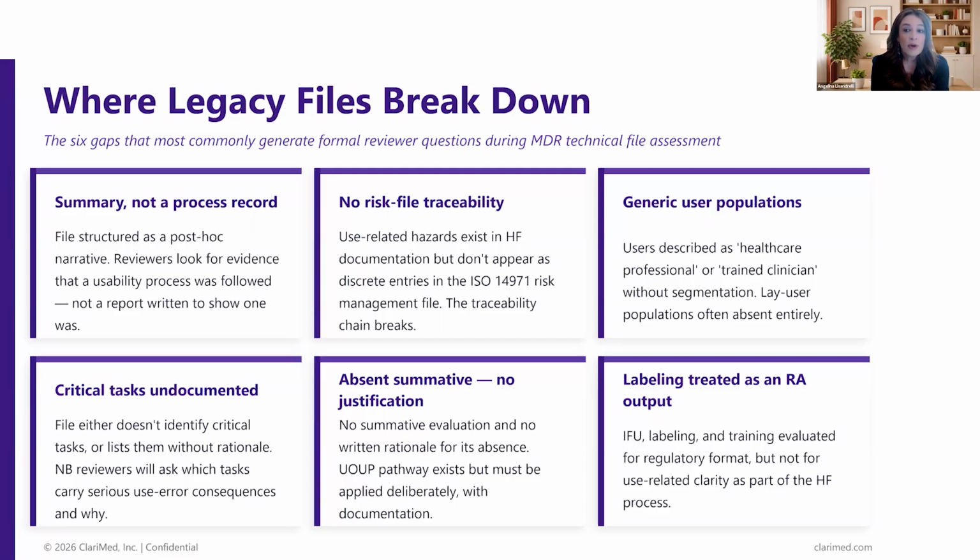And more why it's becoming prevalent for legacy devices later on than when early MDR came back is because of the scrutiny that MDD devices now have to provide more post-market surveillance data. And so because of that, the trends are coming through, the tech doc deficiencies are coming through, and there are patterns here that we see. Make sense?